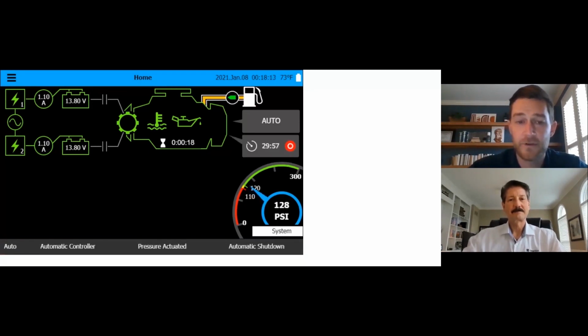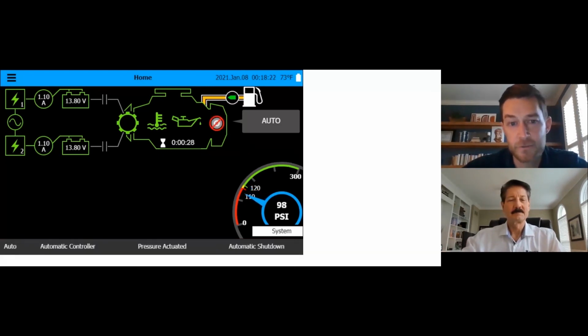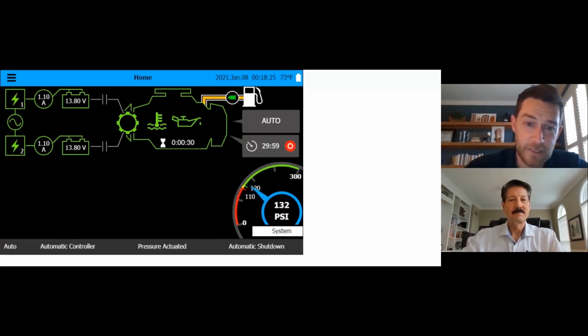And now you can see we have a 30-minute timer. The pump's going to continue to run for 30 minutes as long as it stays above 120 PSI. After that timer has expired, it will shut itself down. If at any time it drops back down like it just did and then goes back up, it automatically resets the timer. So it's got to see a sustained above 120 PSI for 30 minutes before it will shut down. And that timer is adjustable. You can drop it down to whatever time you want it to be. But it has to satisfy those conditions for whatever your preset time is before it will stop.